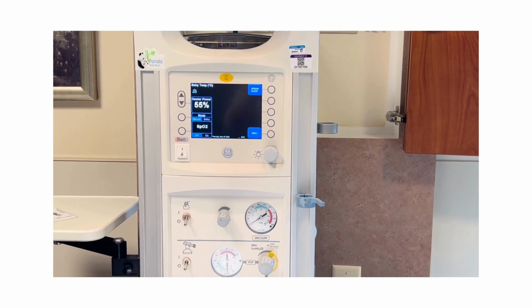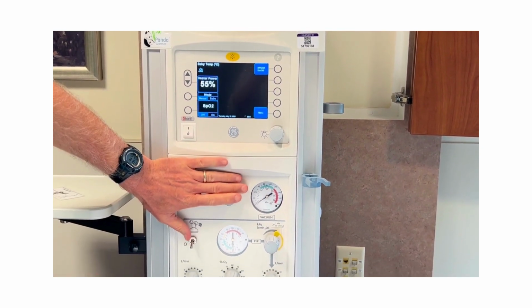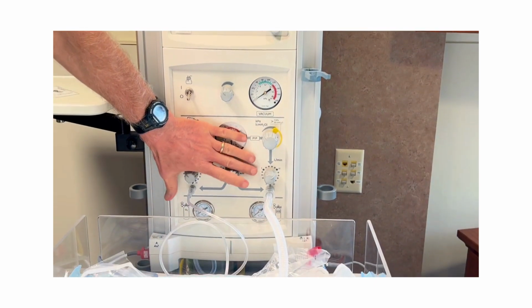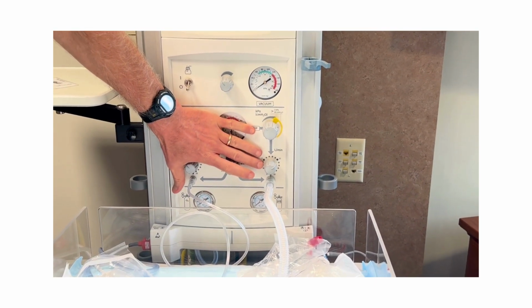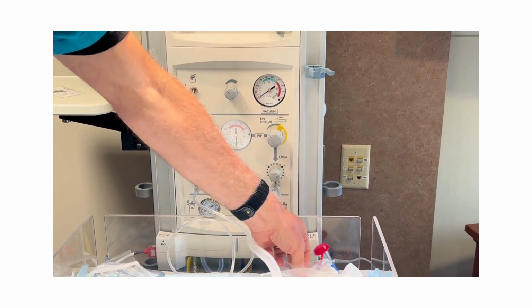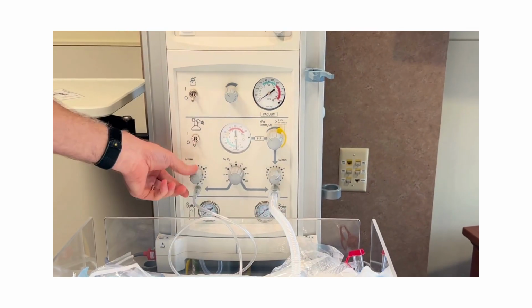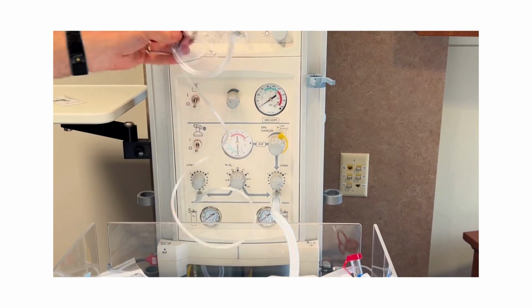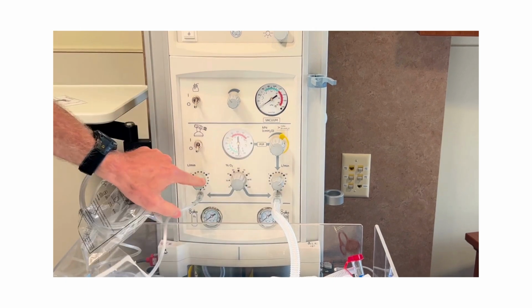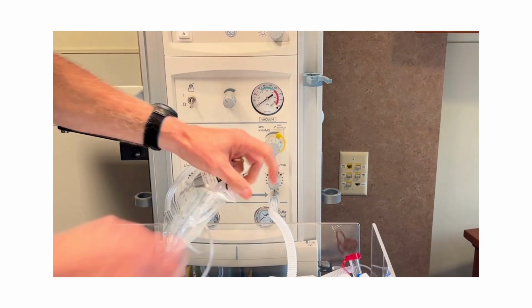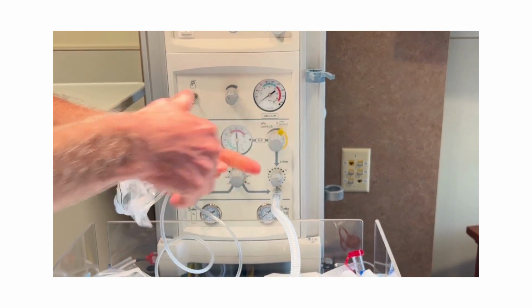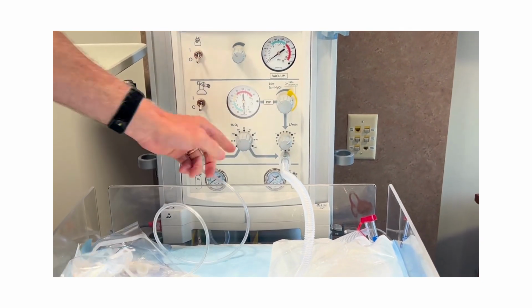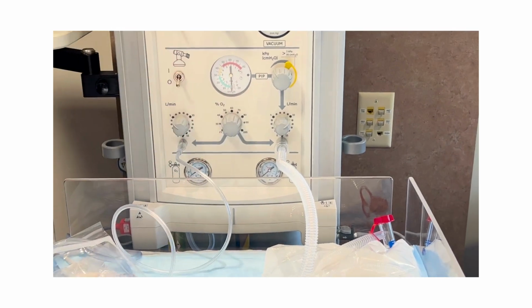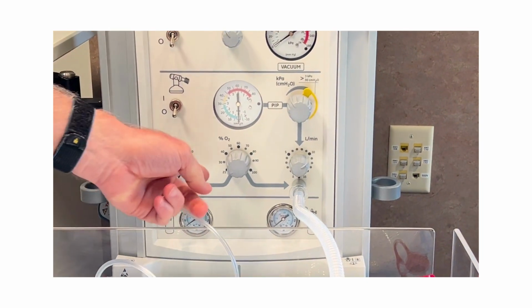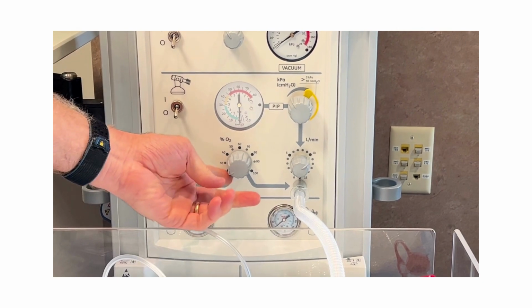And then you're going to want to check your suction and your oxygen delivery, gas delivery here for your Neopuff, and there's a blow-by tubing that we have on these. These are just like flow meters that you would see on a wall with a flow meter. So these are just flow meters, and this is your oxygen percentage gauge. It's a blender, so you can give 21% all the way to 100%.